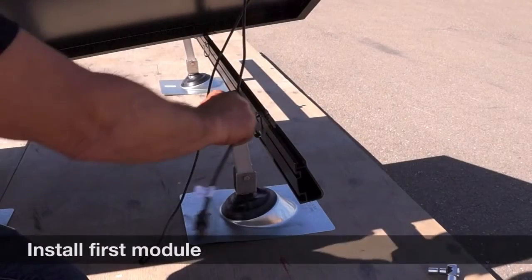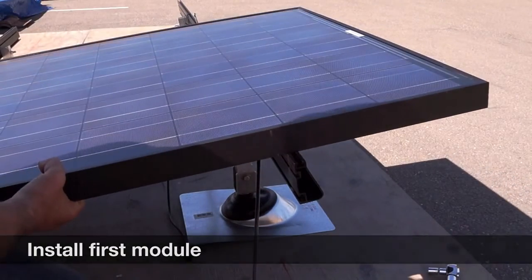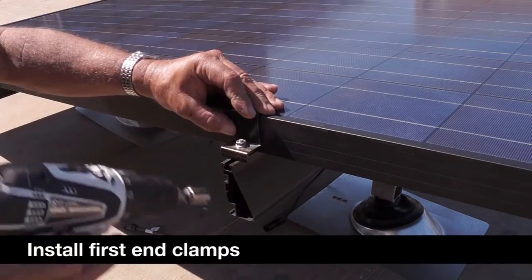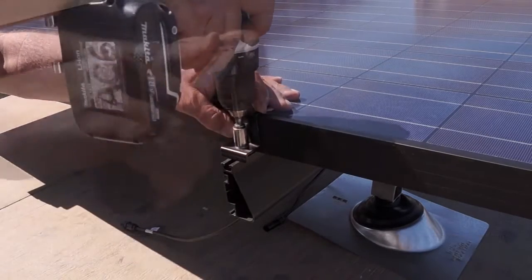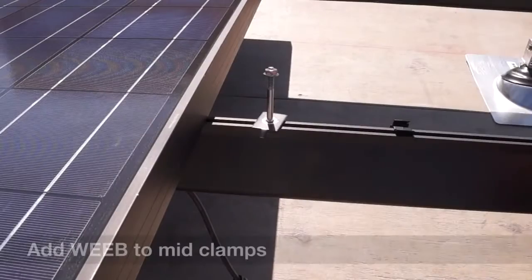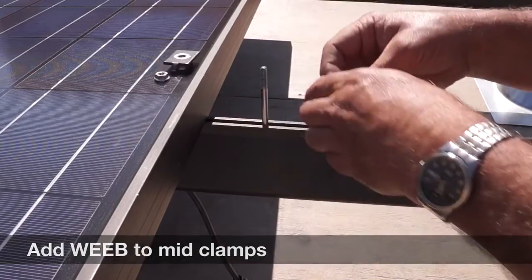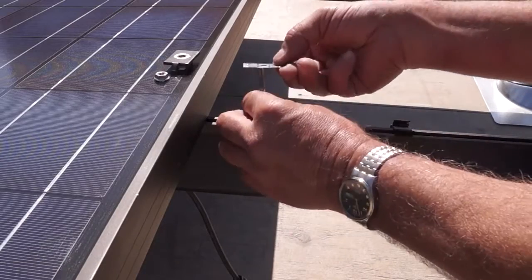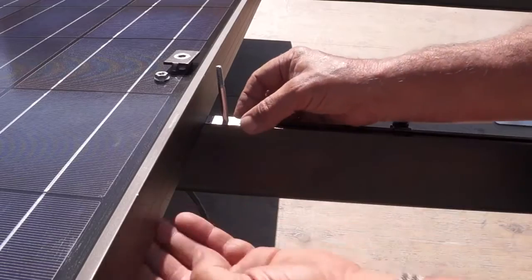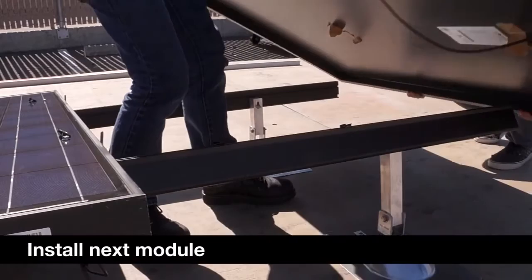Install your first module and align with your 1.5-inch mark at the ends of the rails. Install your end clamps and torque to the required 65 inch-pounds. With your mid-clamp bolts placed against the opposite side of the first module, install your grounding WEEB clip if bonding the module to the rail in your grounding system. Then install your next module.